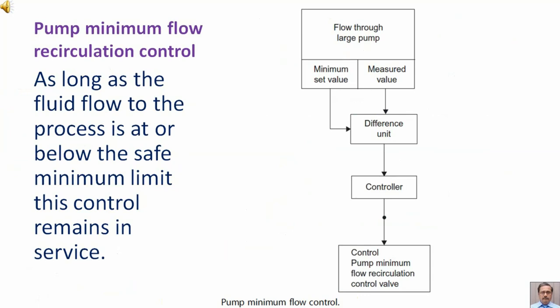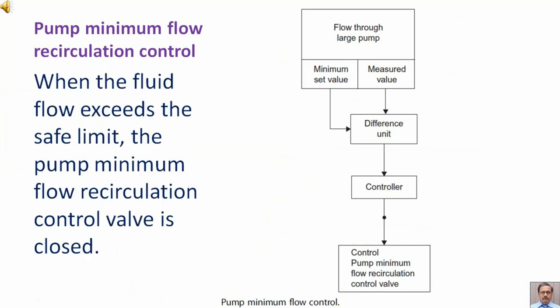As long as the fluid flow to the process is at or below the safe minimum limit, this control remains in service. When the fluid flow exceeds the safe limit, the pump minimum flow recirculation control valve is closed.